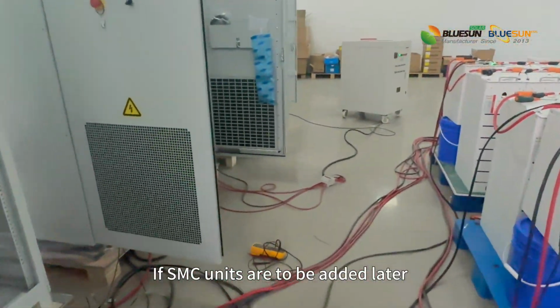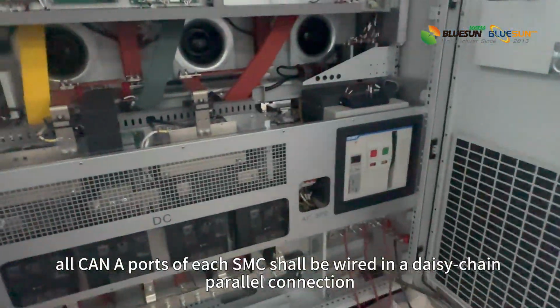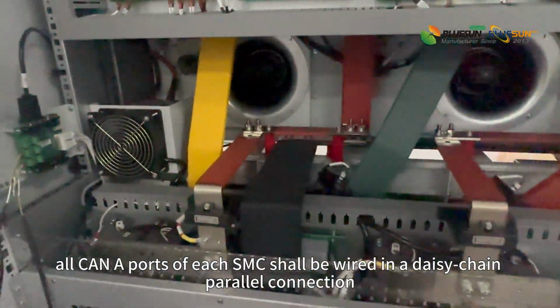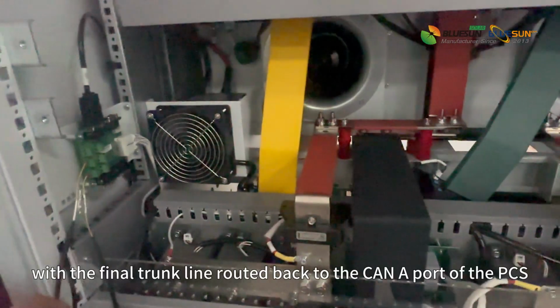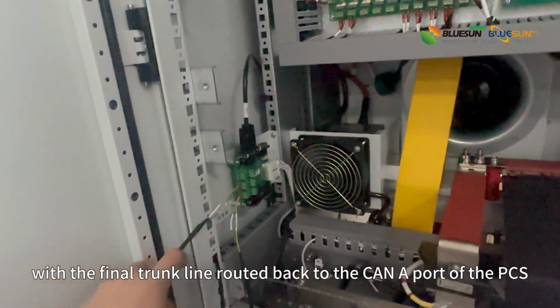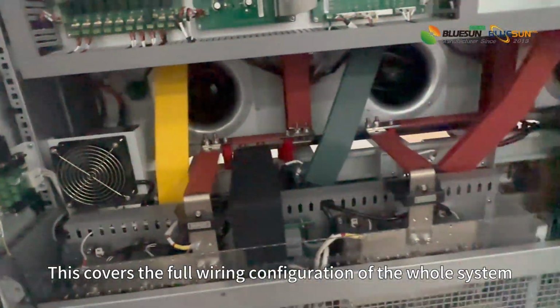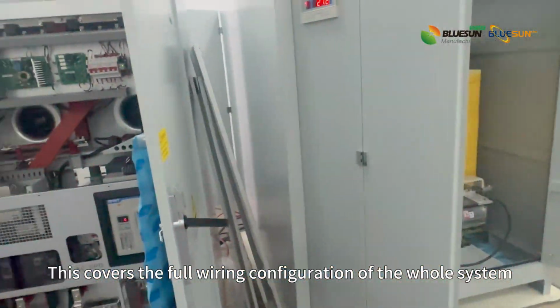If SMC units are to be added later, all CAN A ports of each SMC shall be wired in a daisy-chain parallel connection, with the final trunk line routed back to the CAN A port of the PCS. This covers the full wiring configuration of the whole system.